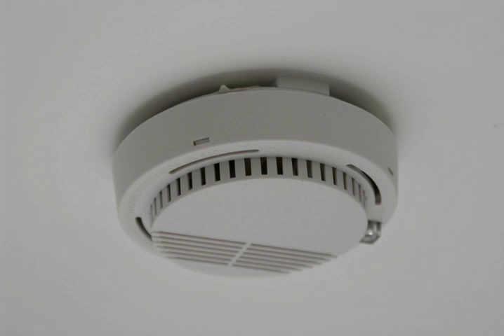A photoelectric, or optical, smoke detector contains a source of infrared, visible, or ultraviolet light — typically an incandescent light bulb or light-emitting diode — a lens, and a photoelectric receiver, typically a photodiode. In spot-type detectors all of these components are arranged inside a chamber where air, which may contain smoke from a nearby fire, flows. In large open areas such as atria and auditoriums, optical beam or projected beam smoke detectors are used. A wall-mounted unit emits a beam of infrared or ultraviolet light which is either received and processed by a separate device, or reflected back to the receiver by a reflector. In optical beam types, the light emitted passes through the air being tested and reaches the photosensor; the received light intensity will be reduced due to scattering from particulates of smoke, airborne dust, or other substances. The circuitry detects the light intensity and generates the alarm if it is below a specified threshold, potentially due to smoke.